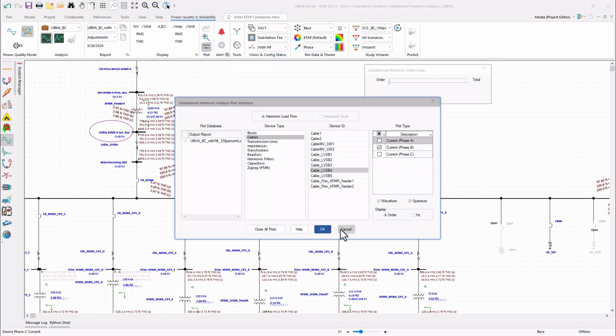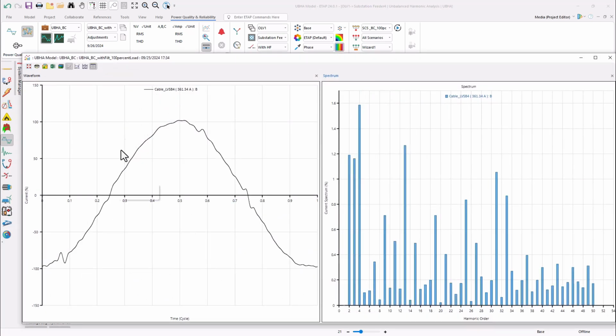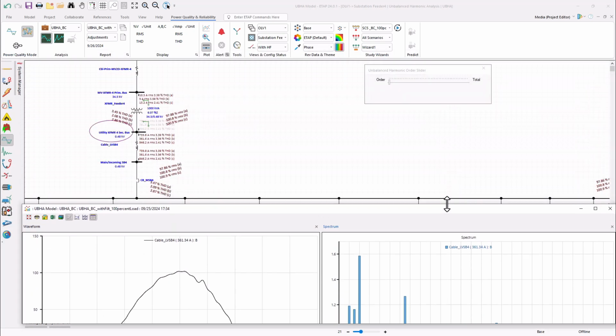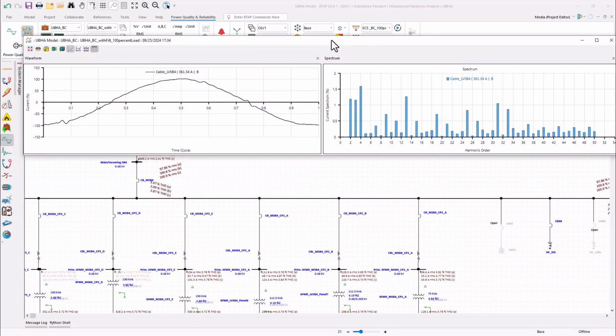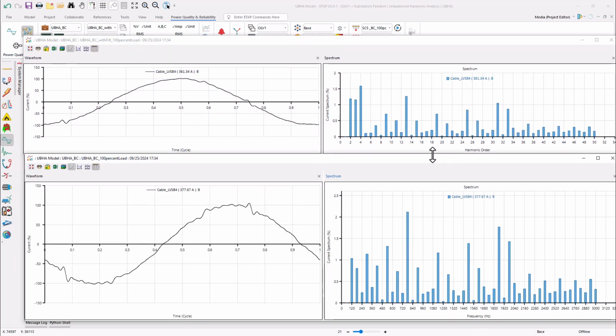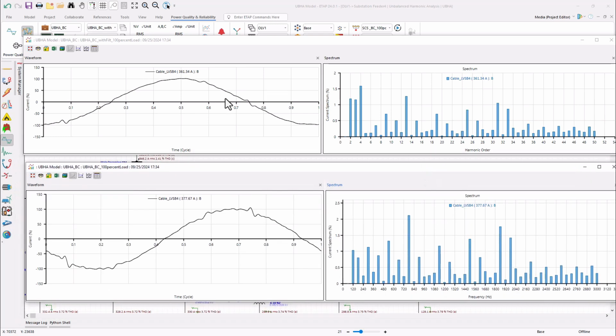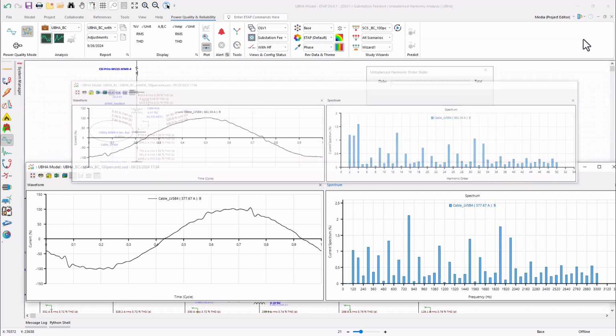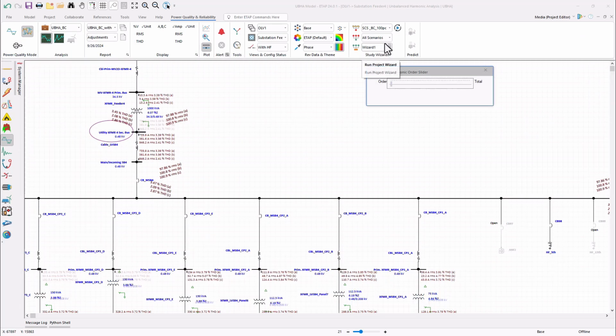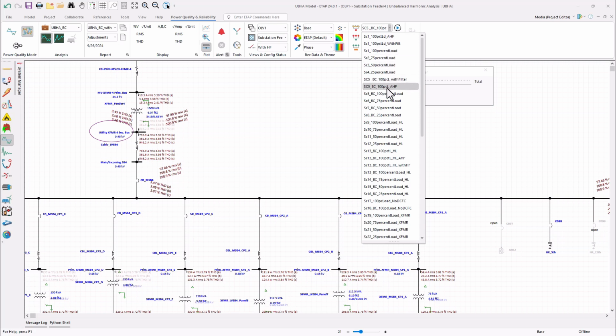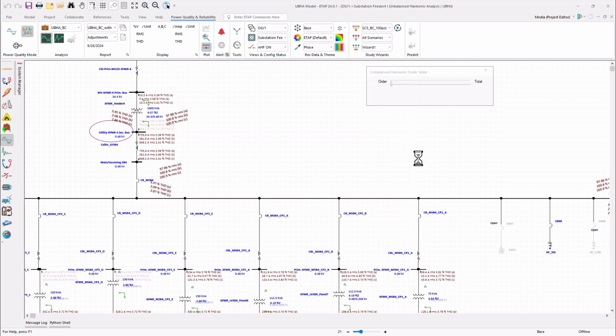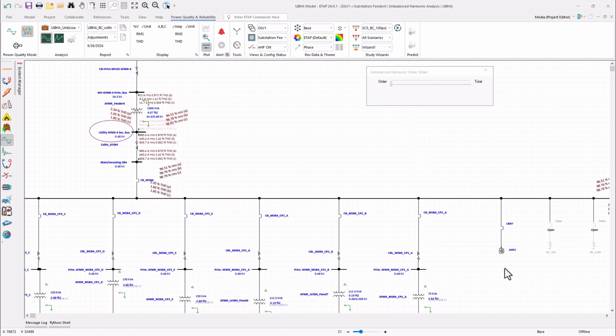Let's do it for the order. If you notice, the waveform distortion has reduced significantly. This was the one without the passive filter setup, and the one above is the one with the passive filter in the system. So let's minimize these and now run another scenario with active harmonic filter. So if you notice, there's results here from this case with active harmonic filter installed. The voltage distortions at this bus got mitigated significantly, and the current distortions have been reduced significantly as well.